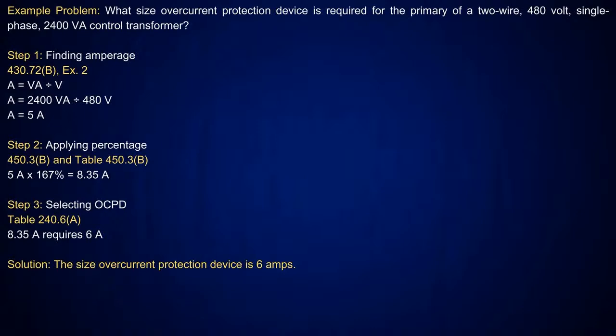So what they're going to tell you in 430.72B exception 2 is, basically, I need to determine my amperage. So this is very simple. You just get the VA of the transformer, divide it by the voltage, there's your amperage. So we always get the amperage first. And then you're going to go back and look at table 450.3B. Okay?